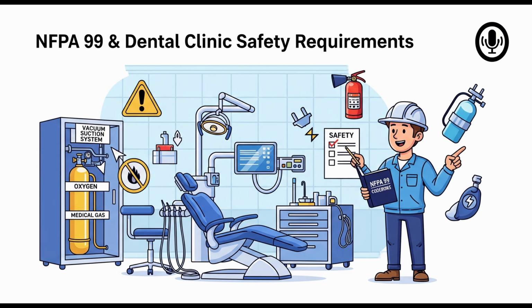Okay, based on our reading of the Category 3 and dental-related sections like 5.3 and 15.4, piped medical gas and vacuum. You must have these systems designed and installed per the code's Category 3 rules. That covers materials, joining, like brazed copper with nitrogen purge, valving, gas-specific outlets, warning systems. You must have the specified source and area alarms located appropriately under surveillance during operating hours and powered by an emergency source. Gas cylinder storage. You must store cylinders according to the rules: proper location, construction, security, temperature control, physical restraint, and critically, strict separation from ignition sources and flammables.